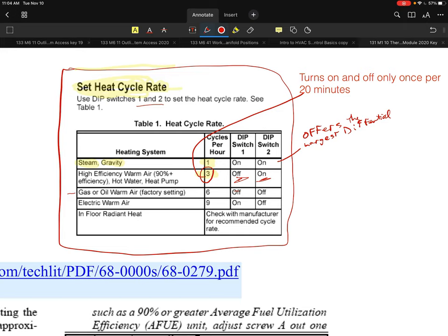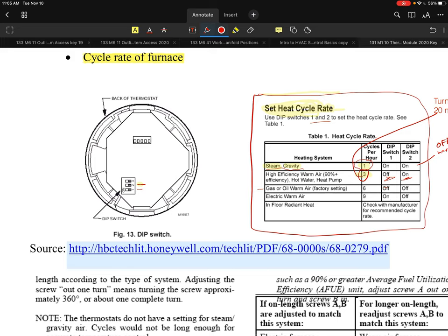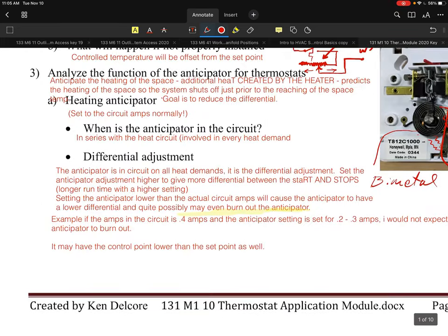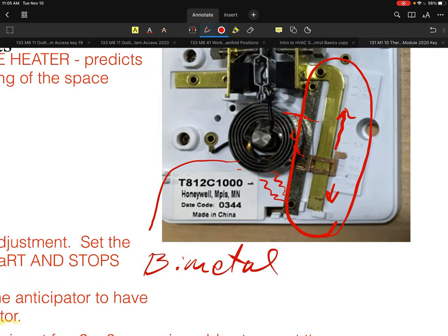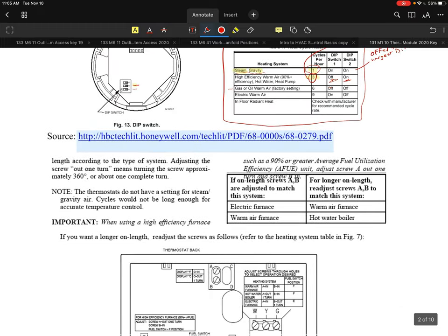If a furnace should only cycle three times per hour but is set to six, eight, or nine times per hour, the igniter alone activates three times as often — potentially shortening component lifespan by a third. What I typically do with an oversized furnace is intentionally set the cycle rate to a lower number. That's my only way to control the differential without changing the furnace — setting a lower cycle rate effectively does the same thing as the anticipator adjustment we discussed earlier.